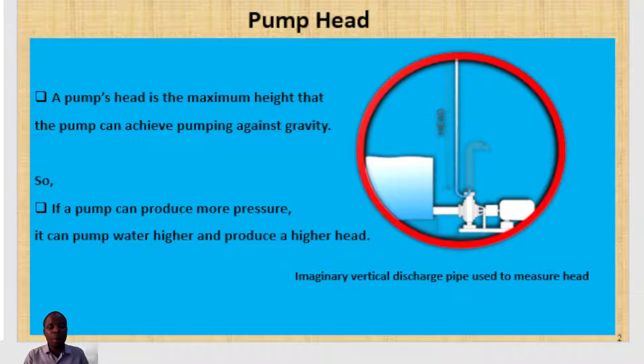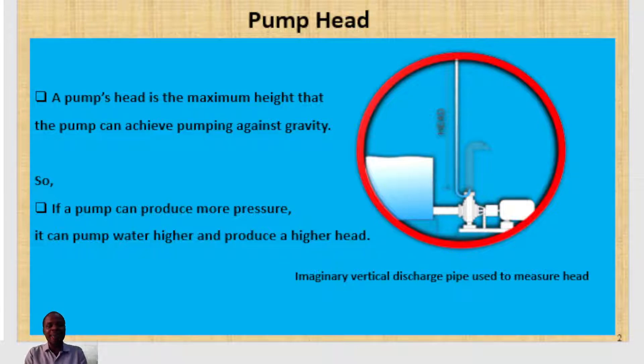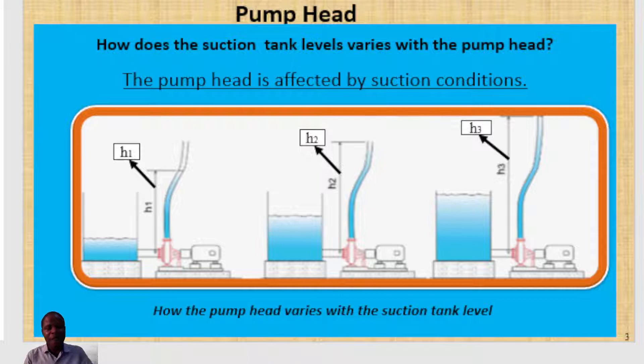That height to which a particular centrifugal pump can raise the water to is called its head. If a pump can produce more pressure, it can pump water higher and therefore produce a higher head. So that maximum height that the pump can achieve pumping against gravity is what is referred to as the pump head. Now, I want you to see how this pump head varies with your suction tank level, because this has a huge impact on your pumping operations.